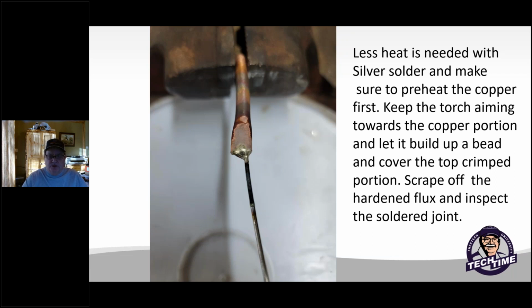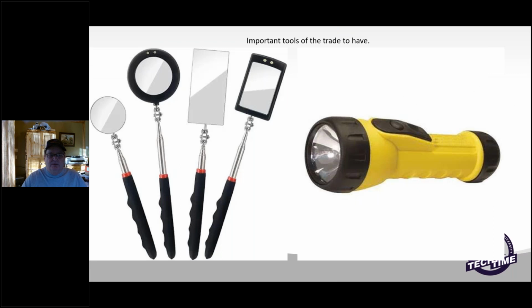So again, when you're done with these, especially with this silver solder, scrape it off because you can get some residue of burnt paste flux and you may miss a leak. So we clean that off again, then use your mirror and double check and inspect the solder joint. Again, most important tools of your trade: visually look. Make sure you've got a good soldering joint and go through your process of evacuation, micron gauge, nitrogen. Nitrogen should be flowing through the tubing at a really low pressure while you're doing your soldering. Make sure it's open going through, use the proper techniques that you've used, and you should be set and good to go.